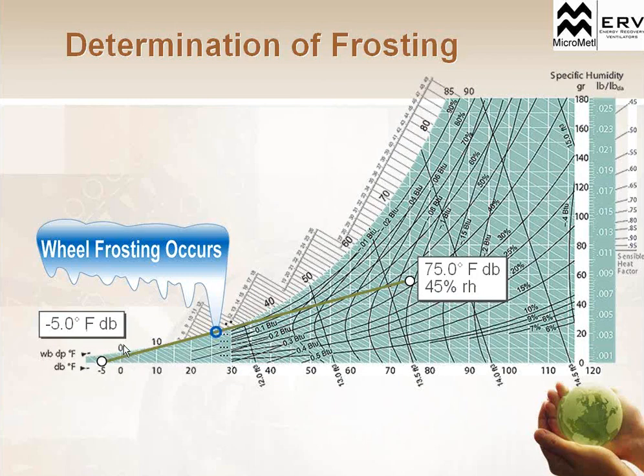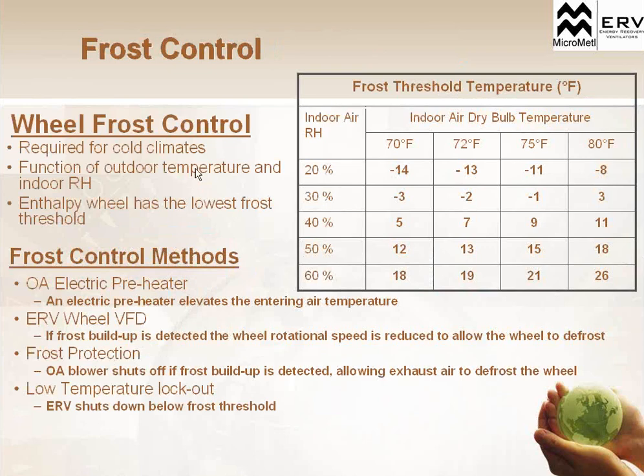So we can do some type of heating of the outside air, an electric preheat before the coil, to reduce that as well. But most typically, in a frosting situation, we could shut off the outside air coming in. We would recirculate that inside air to defrost the wheel itself before we brought in more outside air. There's a couple of different ways to take care of that, and we would do that with the design itself.